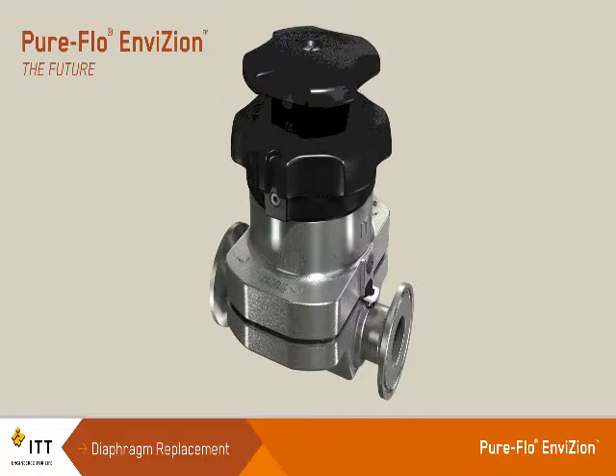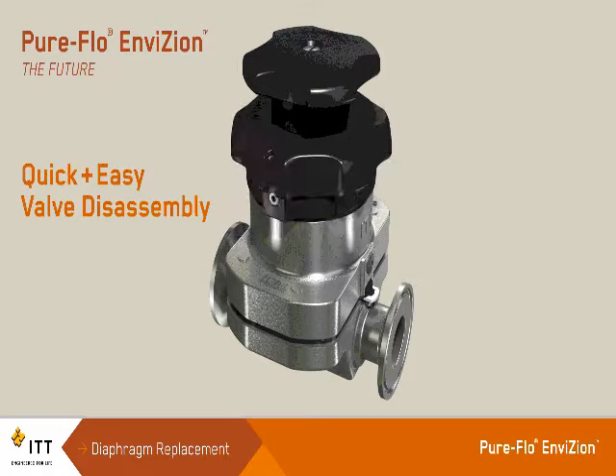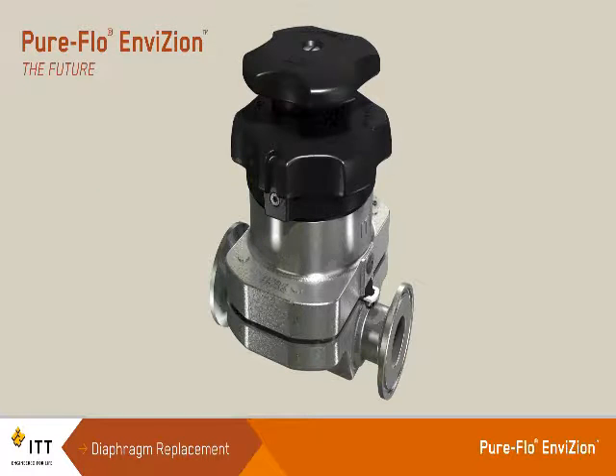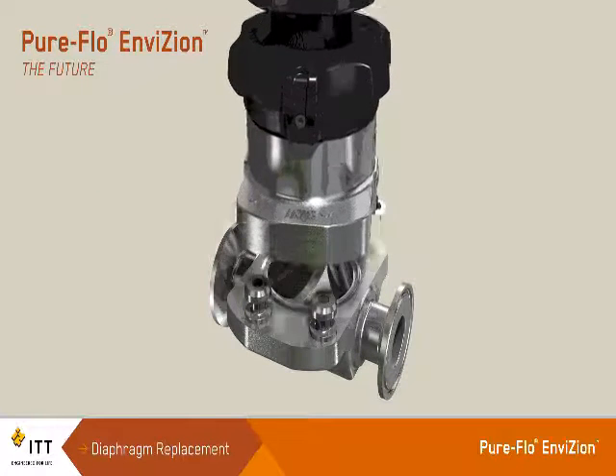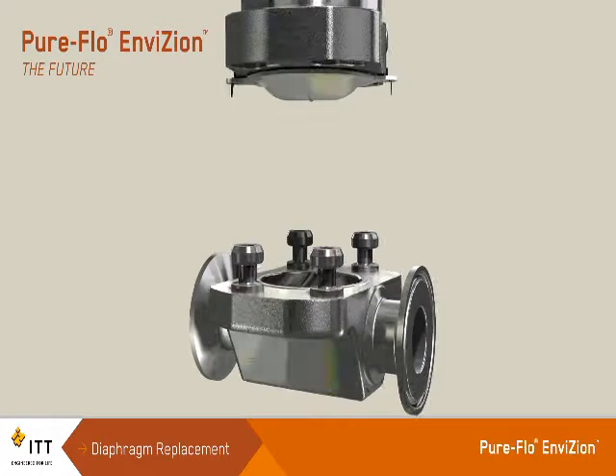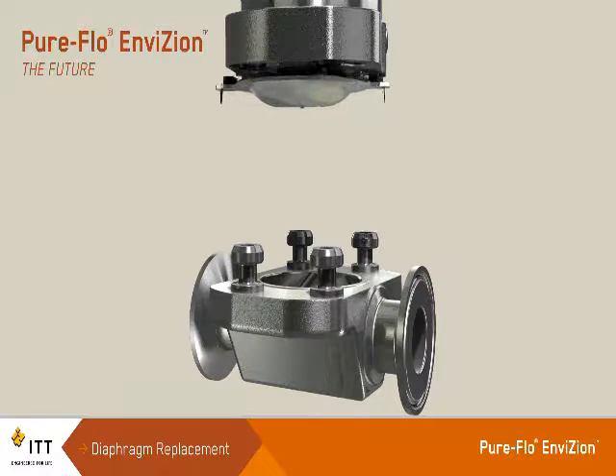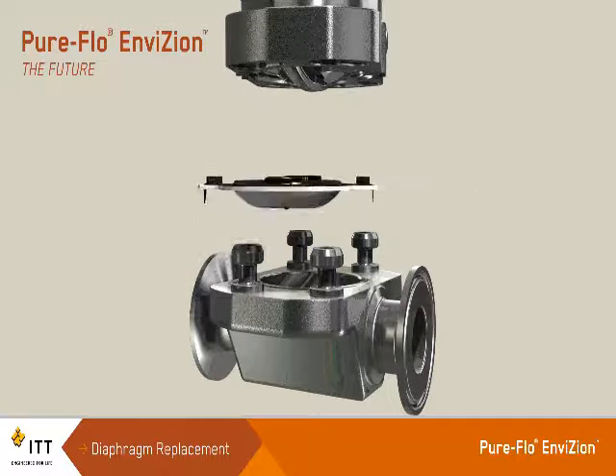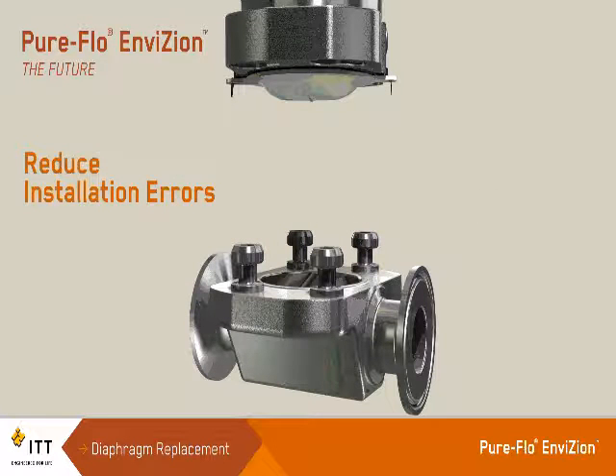The Pure-Flo EnviZion utilizes a stud and key slot concept that allows for quick and easy valve disassembly no matter where the valve is installed. No longer will the challenges of fastener access or handling of loose parts exist, as the fasteners have been eliminated. Diaphragm replacement has been simplified to reduce installation errors, assuring a properly installed diaphragm.